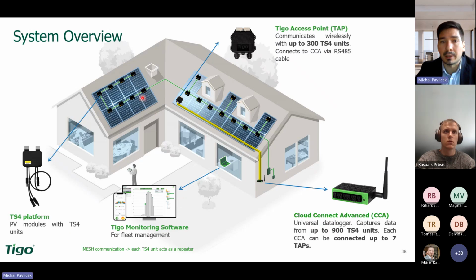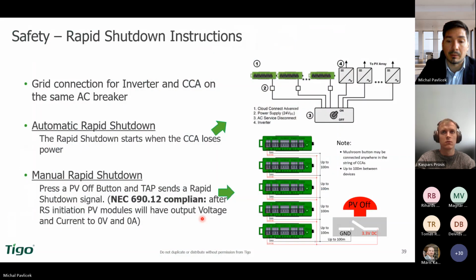When you are on a typical small residential rooftop, like this one, for instance, you would put probably the TAP somewhere here in the corner to be able to monitor all these optimizers. In case there is some barrier which is maybe preventing it from seeing the last optimizer, we can ask our technical support to set a different frequency, or you potentially just move it maybe one module right to also catch the signal here. Then you go with this cable to CCA and you have the data already on the monitoring. Very intuitive, very easy. You have one single app on your mobile phone where you can commission everything and set.